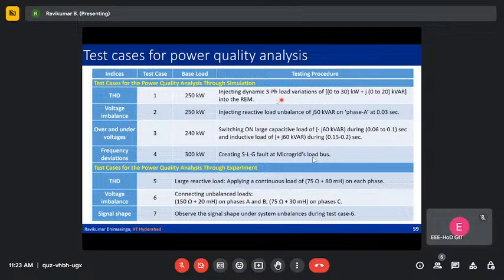There is a procedure. According to that procedure, we have a base load of 250 kilowatt, and what we are doing is injecting a dynamic 3-phase load of 0 to 30 kilowatt and 0 to 20 kVAr into the renewable energy based microgrid. Whenever these load variations occur, P and Q variations, we check how THD is affected.